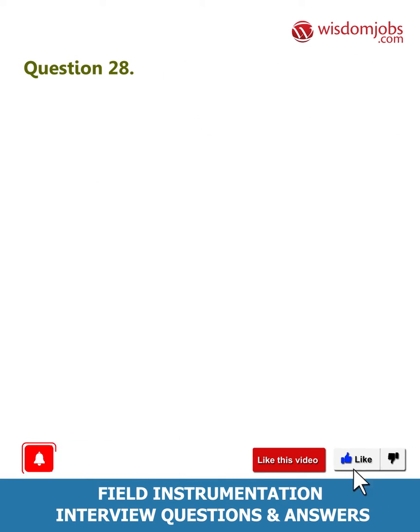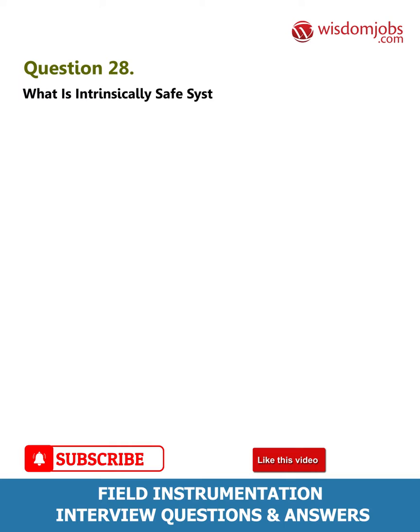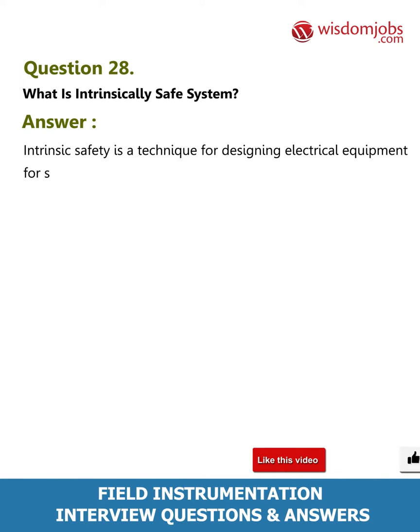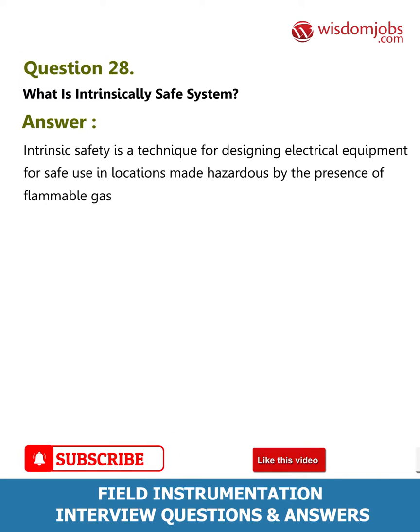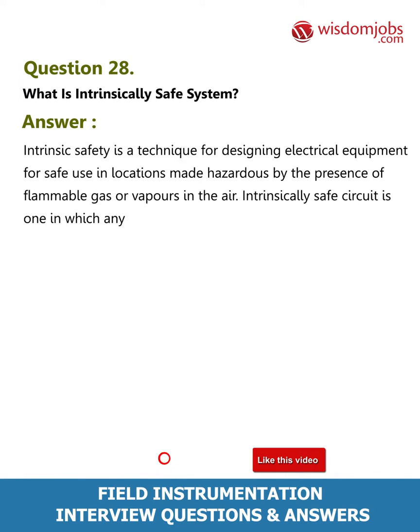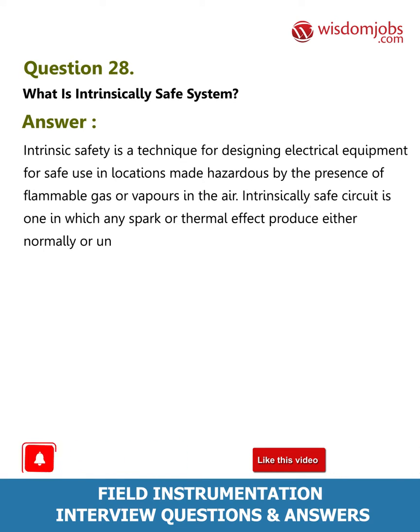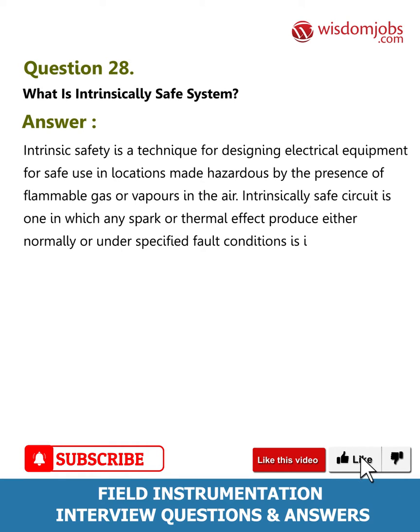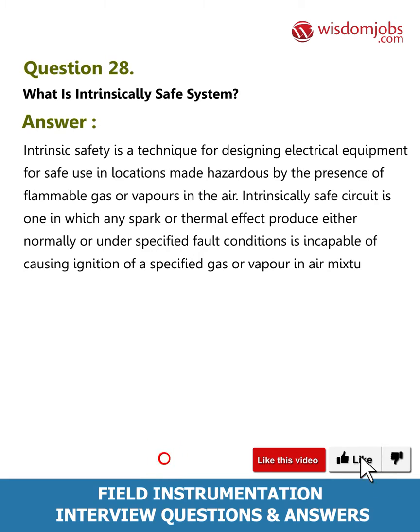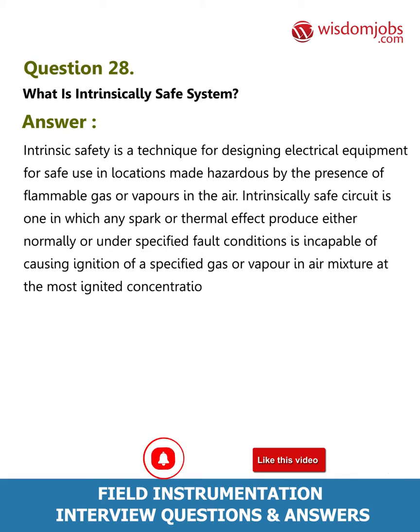Question 28: What is an intrinsically safe system? Answer: Intrinsic safety is a technique for designing electrical equipment for safe use in locations made hazardous by the presence of flammable gas or vapors in the air. An intrinsically safe circuit is one in which any spark or thermal effect produced either normally or under specified fault conditions is incapable of causing ignition of a specified gas or vapor in an air mixture at the most ignitable concentration.